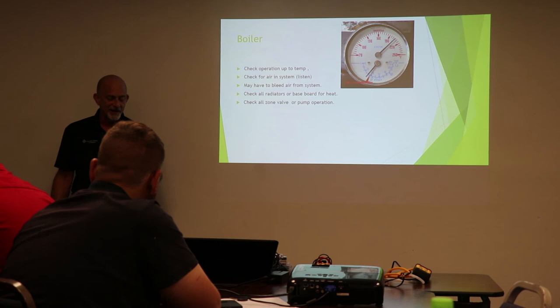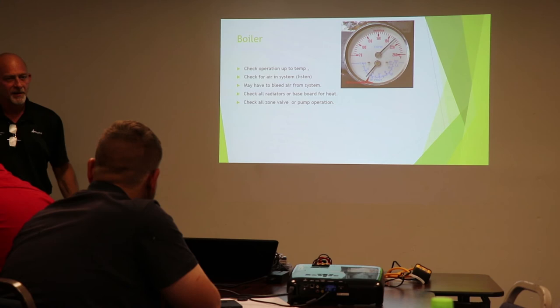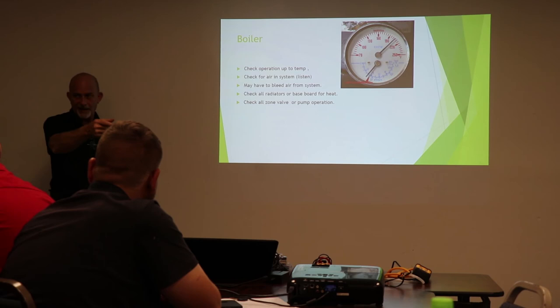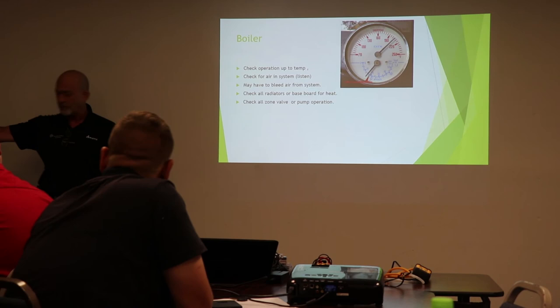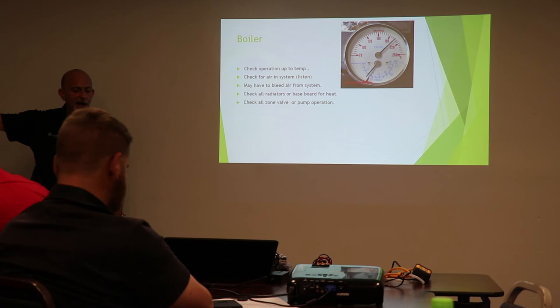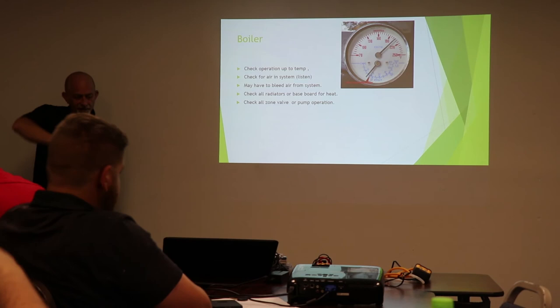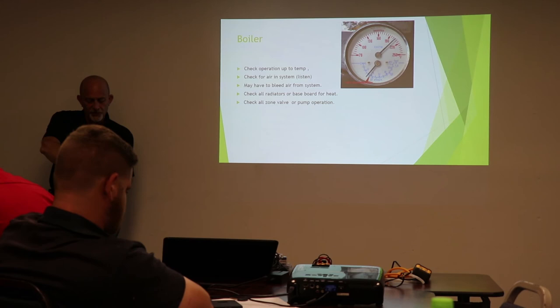I used to carry self-piercing valves with me. Copperfin baseboard has a cover on it, right? Proper way to do it is with a vent 90, because you normally come up from the basement, through the baseboard. You may go to another one, but then you go back down. So you need a place to vent it. So you have a vent T or a vent 90. But if you don't have that, a little saddle valve, self-piercing, find it on there, bleed it out. Once we get the air out, shut it down, put our cover back on. The next time, you know you can do it.